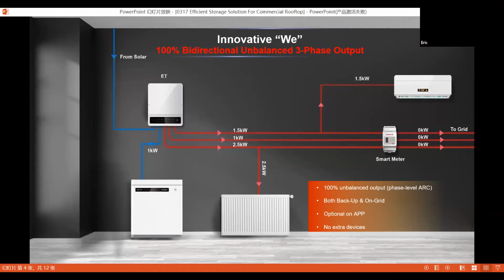Like the picture shows, if the home load for phase 1 is 1.5 kilowatts (the air conditioning), phase 2 has no load, and phase 3 has a load with capacity of 2.5 kilowatts, the total load is 5 kilowatts. If the solar panel is 6 kilowatts, the ET series can output 1.5 kW to phase 1 and 2.5 kW to phase 3, and use the other power to charge the battery.